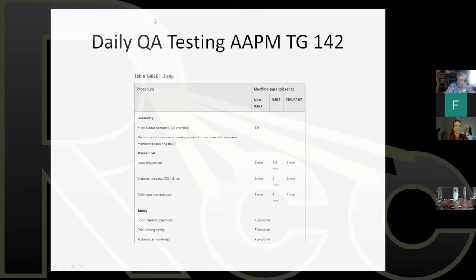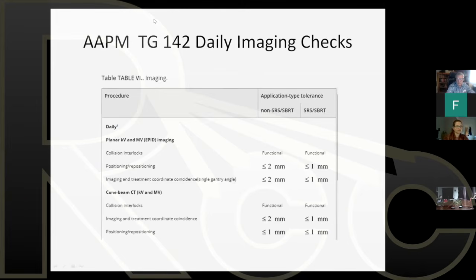Audio visual, very important. You have to be able to see and hear the patient. Now, some of the other tests, which we're going to go into, are the imaging tests that TG142 made specific guidelines on. Planar KV and MV imaging, which is portal imaging, has certain requirements for testing. Of course, there's collision interlocks. Make sure that the collision interlocks are working. If anything touches these imaging panels, then the machine must stop moving because there is a danger of harming the patient if the interlock is not working. Sometimes the patient is very close to these devices and they may contact the patient, and there's a danger of hurting the patient if the interlock is not working.